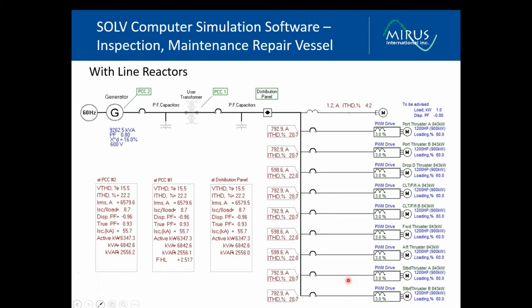Here's an example of a one-line using the SOLV software. Here we have an IMR vessel. From the one-line of the vessel, we've taken all the various variable speed drive loads. Here, the thrusters on the port A side and B side, other thrusters, as well as equipment on the starboard side. And so there are various variable speed drives, various load sizes of the drive systems. We've done this analysis with just a 3% AC line reactor and a little bit of linear load.